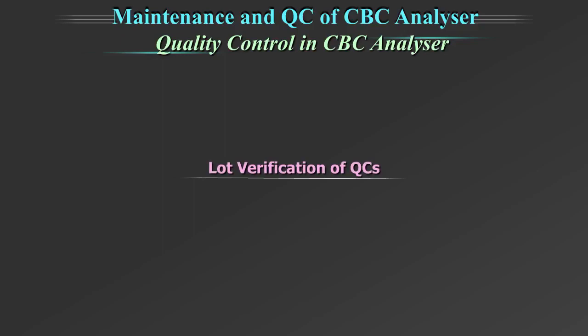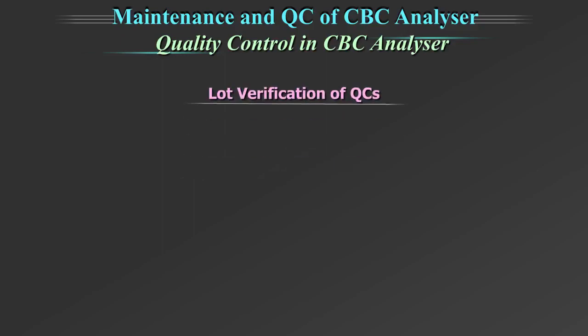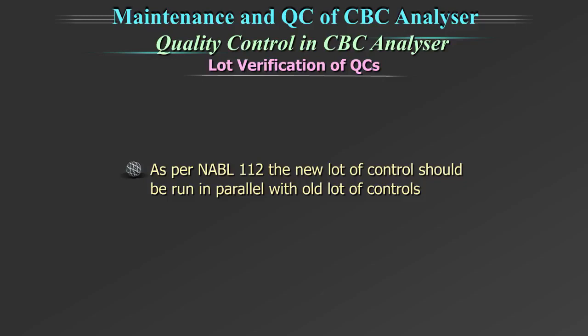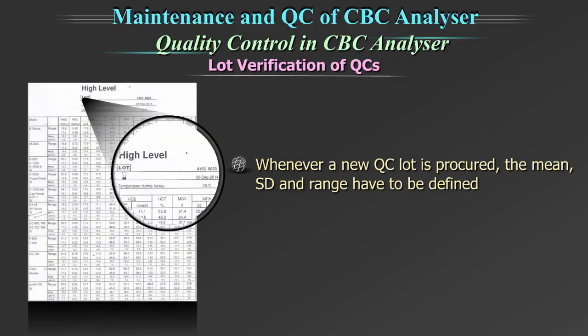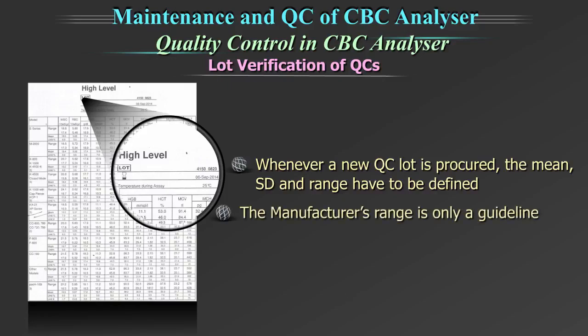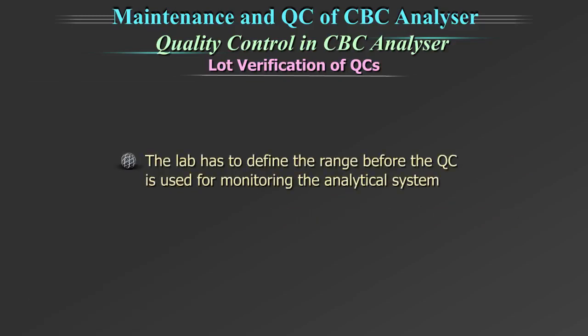Lot verification of quality controls. As per NABL 112, the new lot of control should be run in parallel with the old lot of controls. Whenever a new QC lot is procured, the mean, standard deviation and range have to be defined. The manufacturer's range is only a guideline.